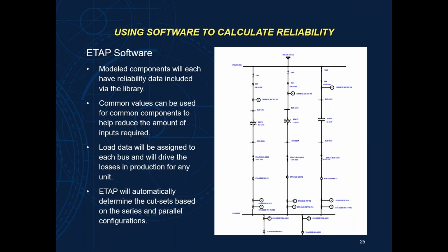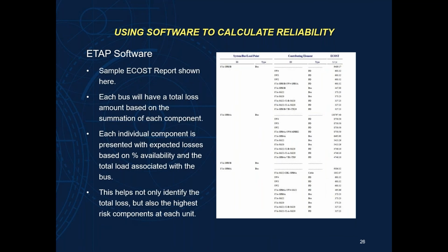So here's a quick example of a software calculation that's been performed before. This is the primary distribution at a refinery where they had 3 feeders that fed the primary switchgear. And I mean, this system is huge. This is just a small snapshot of the top part of the system. So what we did was we got the data for the library, the component failure rates, and the time between failures. We assigned all that information in a library to each component in our system. Once we pulled it into the components, ETAP did everything else for us, and it produced a report that looks kind of like this.